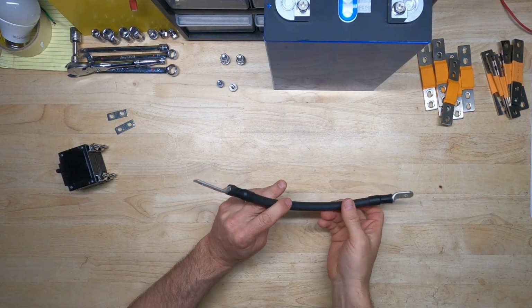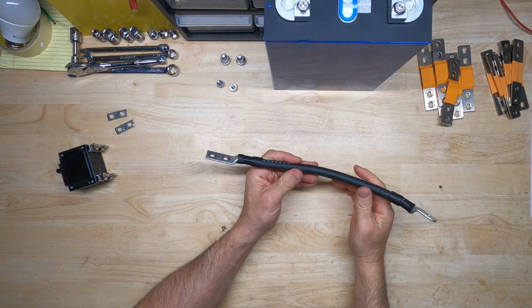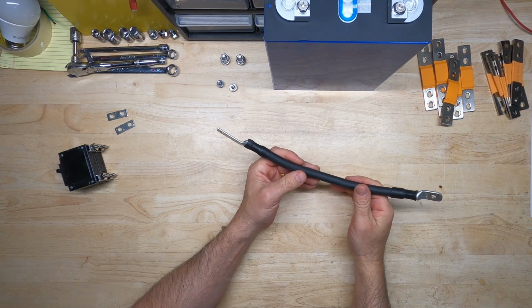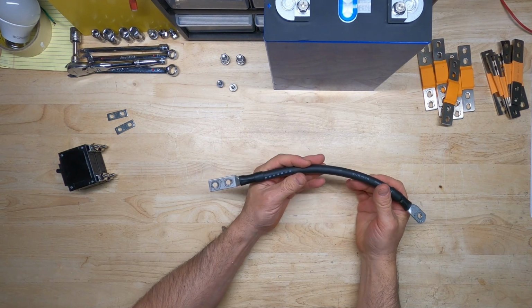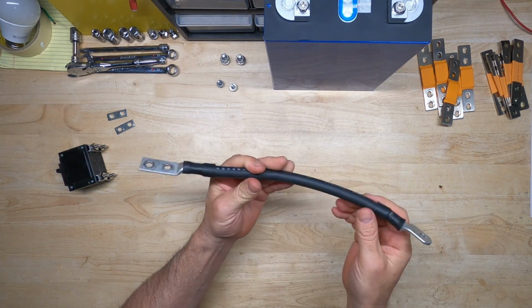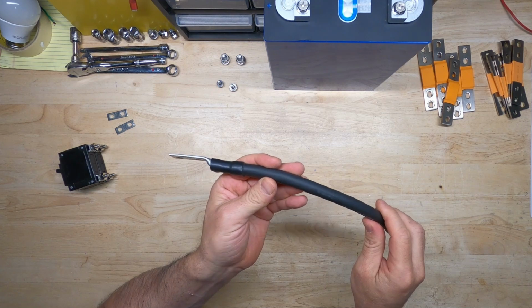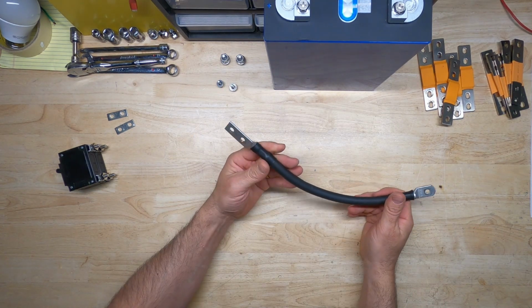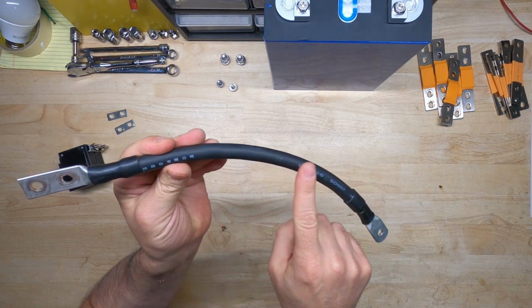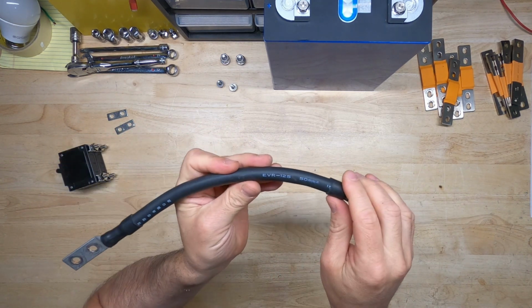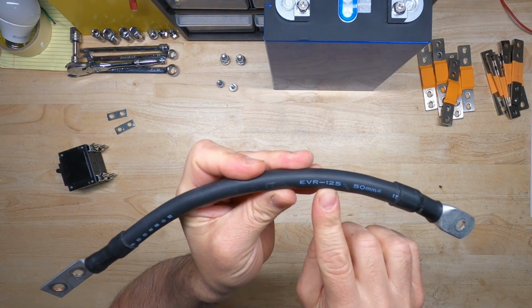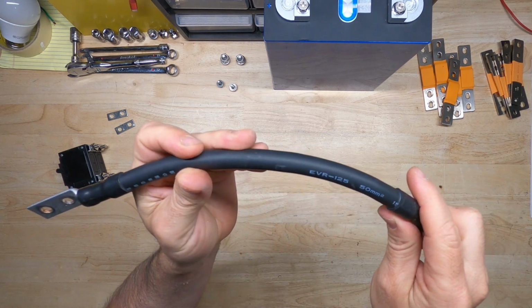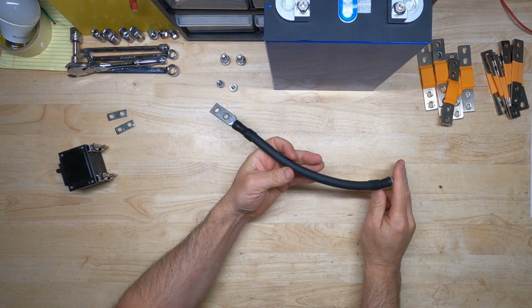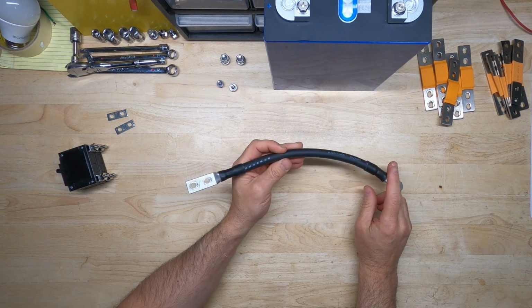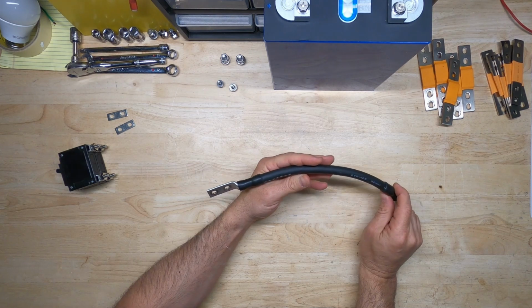Okay, next up is the battery cable. What determines the ampacity in a battery cable, or any conductor for that matter? Well, the length of the cable, not so much. The cross section, how thick the cable is, what material the conductor inside is made out of, aluminum or copper. And also what's very important is the insulating jacket and what temperature it's rated for. There's a 125 printed on here. I'm not sure if that's the temperature rating, but if it was, it would probably be in Celsius, so 125 degrees Celsius. The max temperature we saw on this battery cable was 130 to 140 degrees.